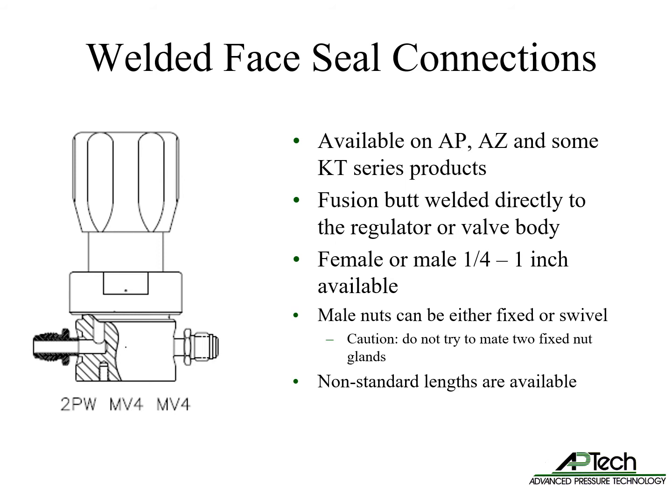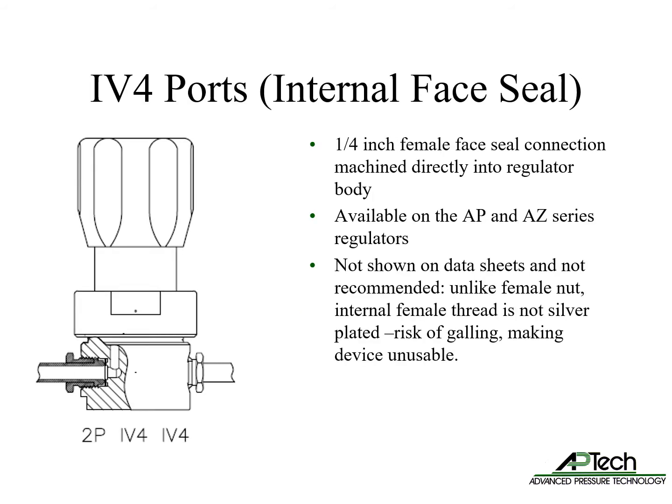Non-standard lengths are available to match face seal to face seal dimension requirements. The IV-4 option is a female 1/4 inch face seal connection machined into the regulator body. It is available as a non-published option but not recommended. Unlike normal female face seal nuts, the internal female face seal is not silver plated. There is a high risk of galling and making the device unusable.